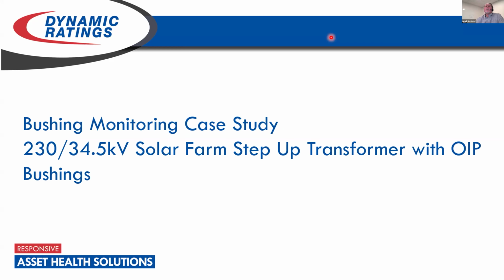Now, I know there's a lot of movement within the industry, because OIP bushings in renewable applications seem to have issues, to go more to a dry type: resin impregnated paper, resin impregnated synthetic. While those do perform better and provide a safer option, I think the verdict is still out as to the long-term performance of those with expansion and contraction and things like that. There are some early indications that maybe that's causing some power factor changes in those bushings.